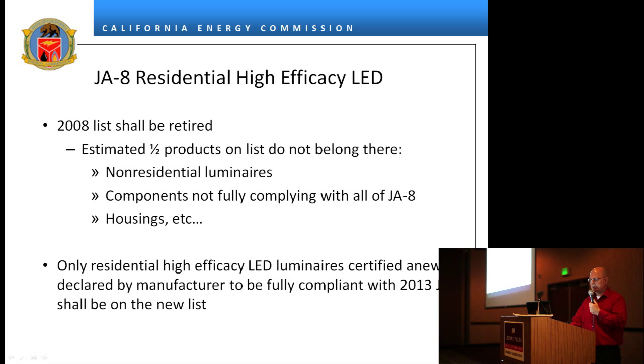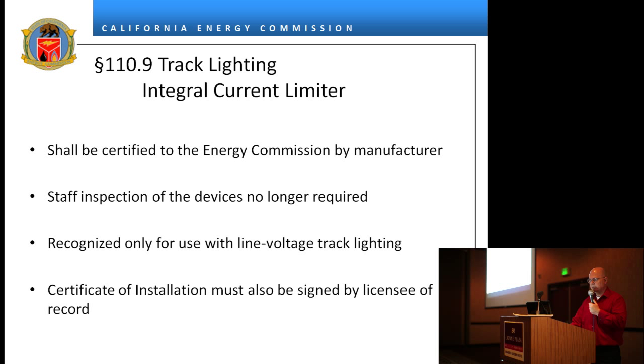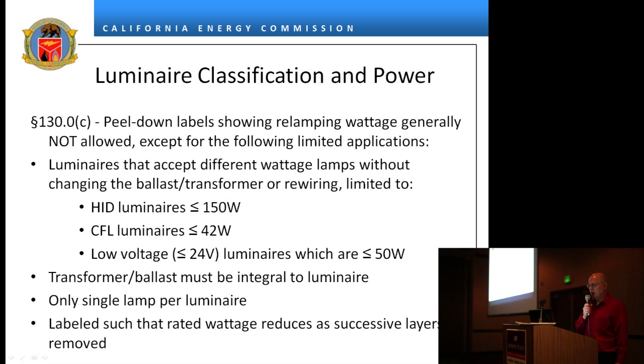Approximately half the products don't belong there — it's only residential. Track lighting and integral current limiters have evolved a little bit. If you currently have track lighting and integral current limiters certified, you will have to recertify your product under the 2013 standards because there have been some changes. Requirements include 24 volts, less than or equal to 50 watts, and the transformer/ballast must be integral to the luminaire. There is only a single lamp per luminaire.